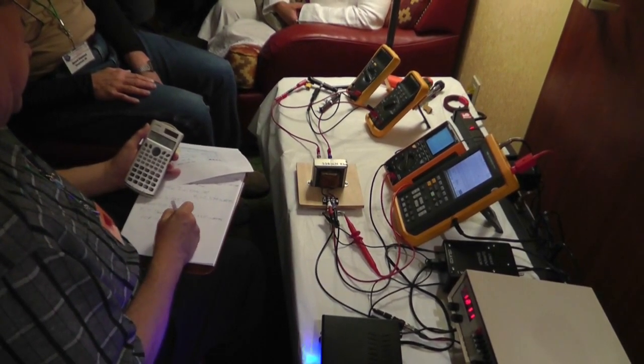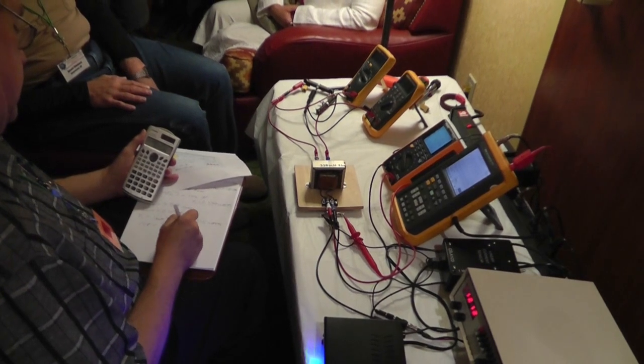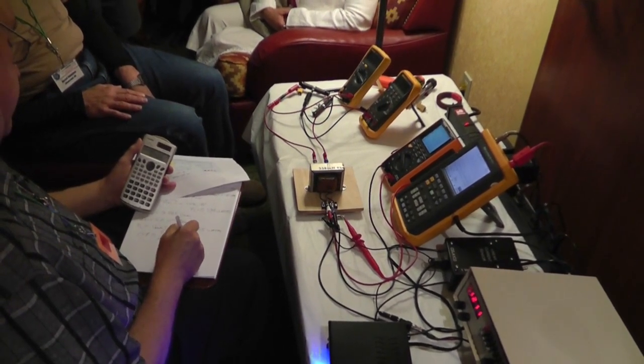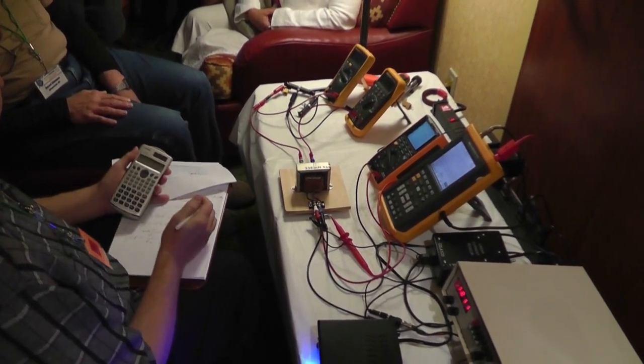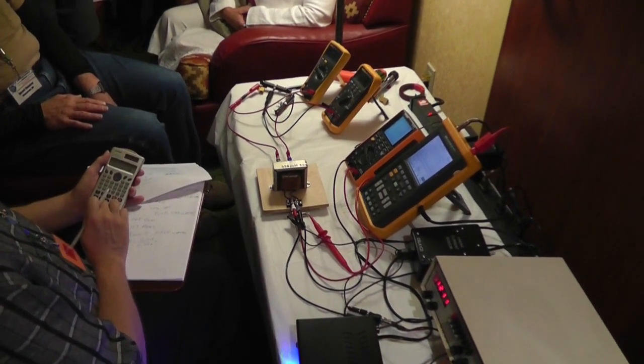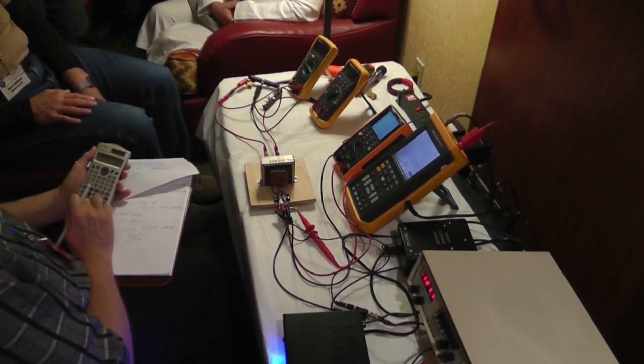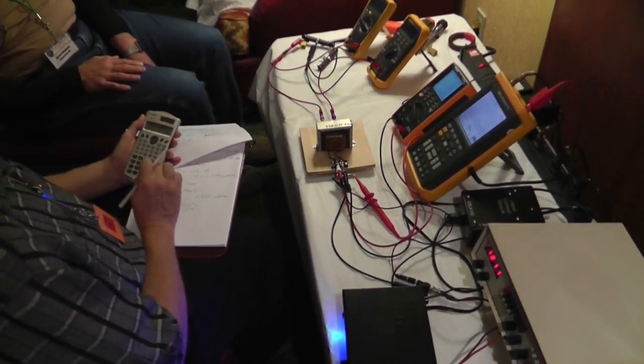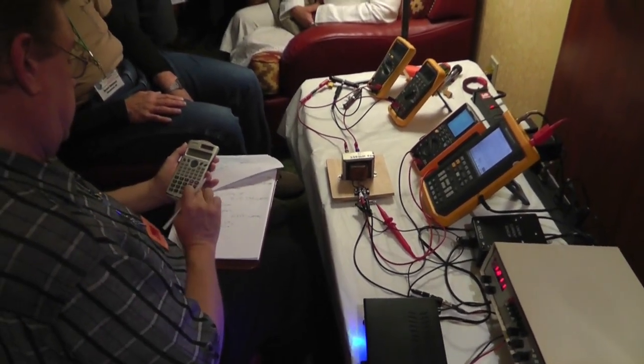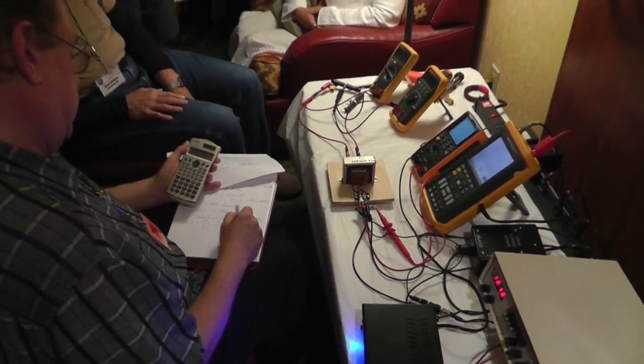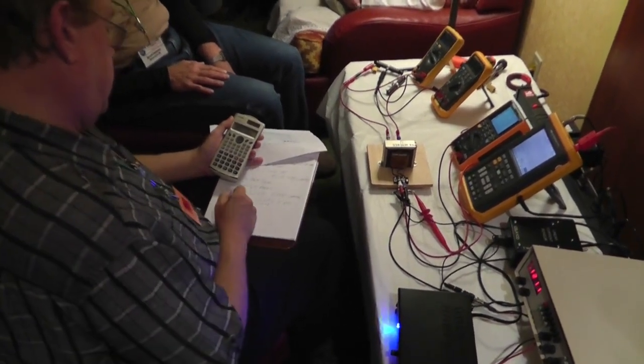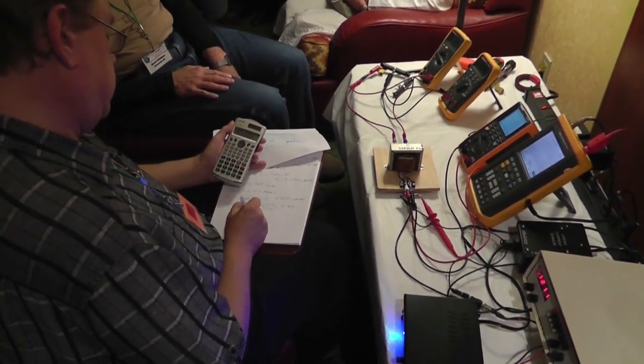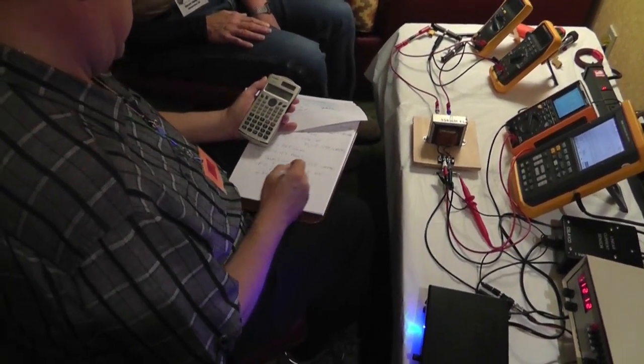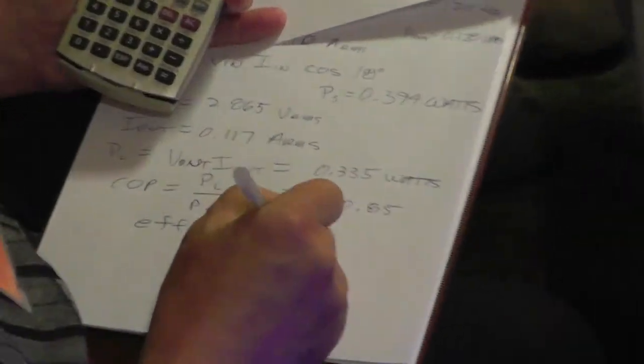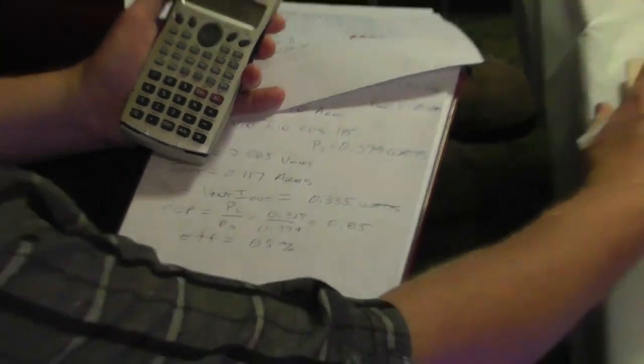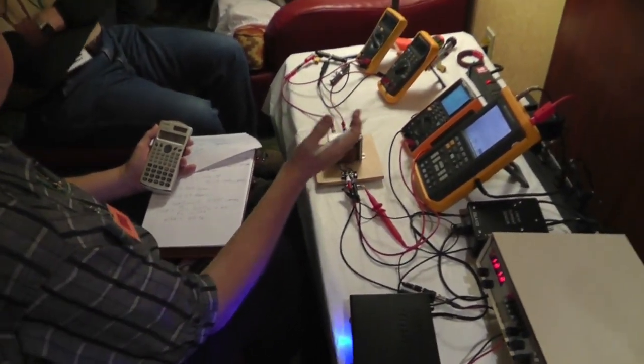Okay, so that's 0.335 divided by 0.394, equals 0.85. Our transformer efficiency is 85%, which is very typical of a traditional transformer.